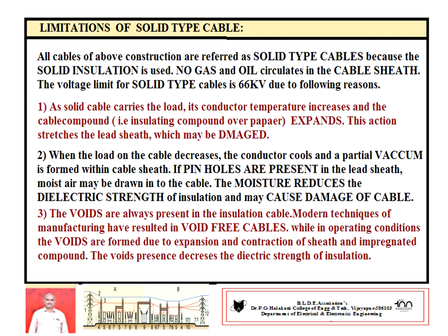This is one point. Second one, when the load on the cable decreases, the conductor cools, or it may be affected by partial vacuum action. Due to this, if pinholes are present in the lead sheath, then moist air may be absorbed by the cable. This is a very unwanted property.